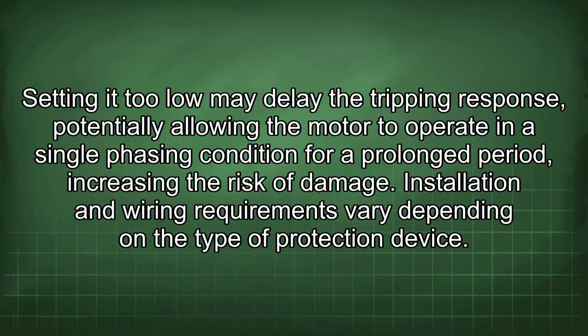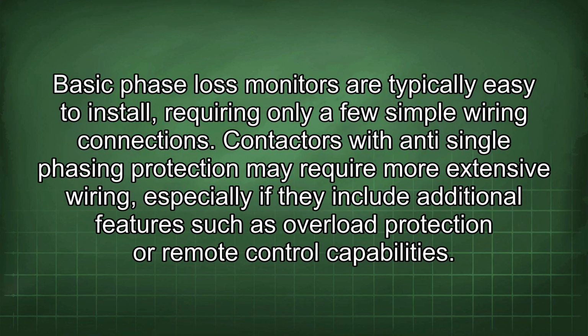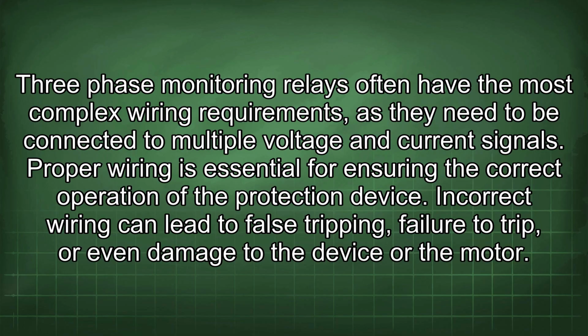Installation and wiring requirements vary depending on the type of protection device. Basic phase loss monitors are typically easy to install, requiring only a few simple wiring connections. Contactors with anti-single phasing protection may require more extensive wiring, especially if they include additional features such as overload protection or remote control capabilities. Three-phase monitoring relays often have the most complex wiring requirements, as they need to be connected to multiple voltage and current signals.